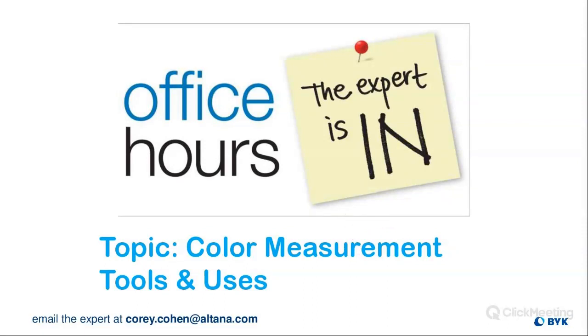You want to, at the very least, be using the same geometry, preferably the same instrument model, preferably a BYK-Gardner instrument. It is very important to use the same geometry. I can't tell you how many times I've gotten a panicked customer whose supplier or customer took measurements and there's a 20 delta E difference between their measurements, and it almost always comes down to one using 45-0 and the other using sphere.